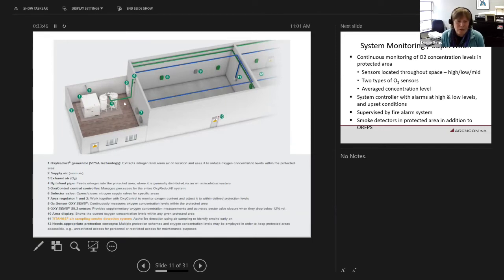The green pipe going across from the two, so you've got the compressors in the larger box, you've got the membrane filtration in the two cylinders. The green pipe in is the nitrogen into the space and the dispersion of that into the space. The blue lines within the box represent the smoke detection units. The small green boxes along the sides of the wall would be your oxygen sensors. So they show an 8 and a 9, the 8 being the oxygen sensors that are blended, the 9 being the secondary checkpoint on the sensor.